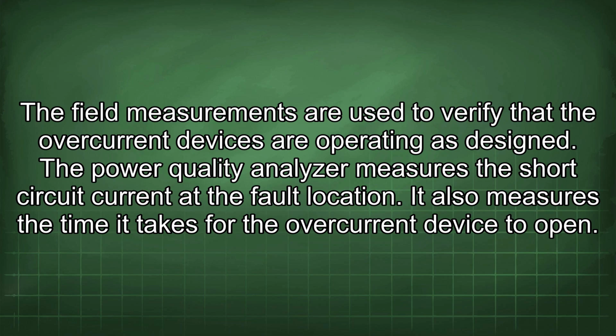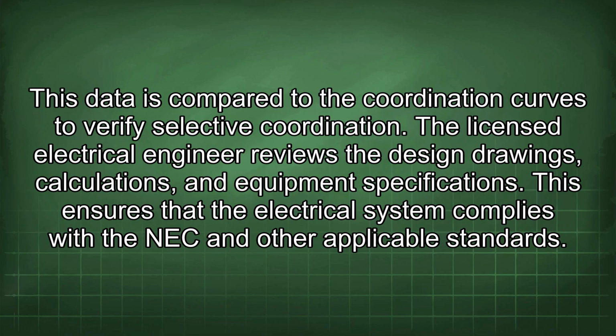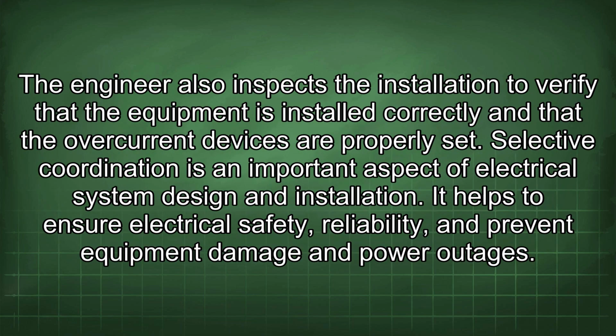The power quality analyzer measures the short circuit current at the fault location. It also measures the time it takes for the overcurrent device to open. This data is compared to the coordination curves to verify selective coordination. The licensed electrical engineer reviews the design drawings, calculations, and equipment specifications. This ensures that the electrical system complies with the NEC and other applicable standards. The engineer also inspects the installation to verify that the equipment is installed correctly and that the overcurrent devices are properly set.